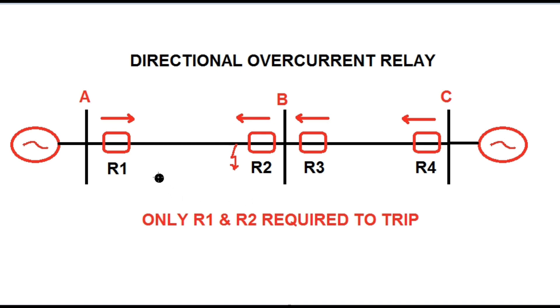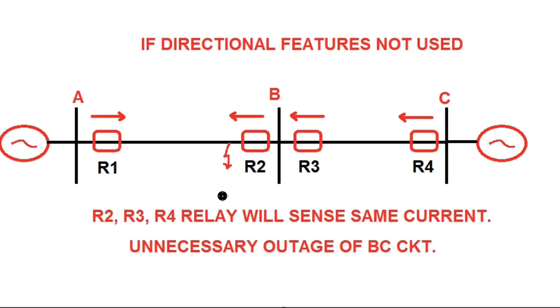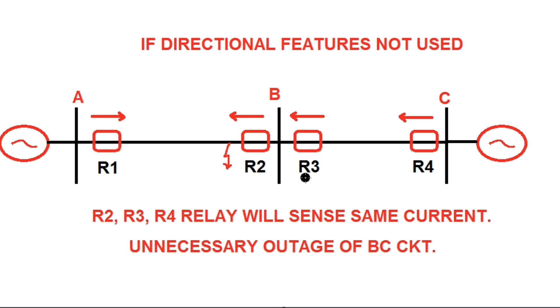Due to the fault, relay R1 will sense it, and also relay R2, R3, and R4 will sense the same current as the source is connected at substation C end. But only relay R1 and R2 are required to trip their respective circuit breakers to isolate the faulty circuit. If non-directional relays are used, relay R2, R3, and R4 will all trip, causing unnecessary outage of circuit BC.